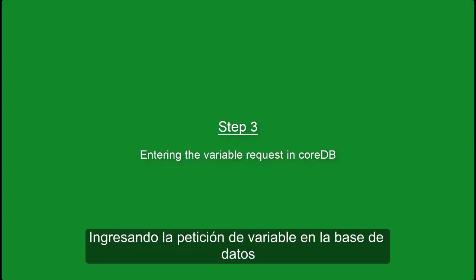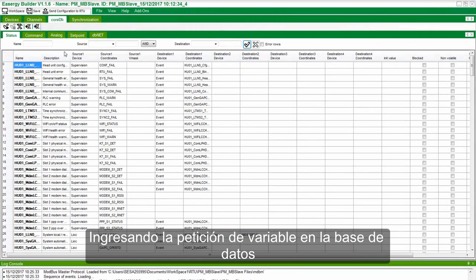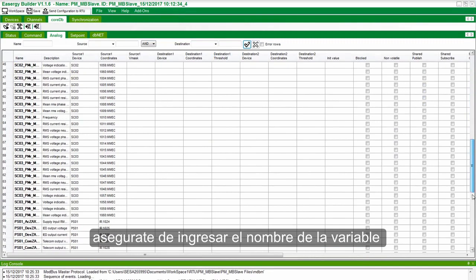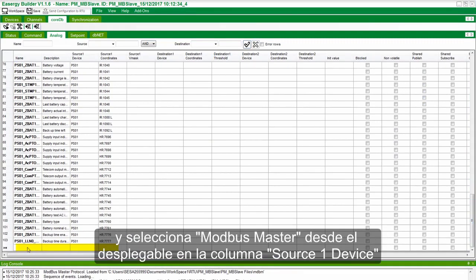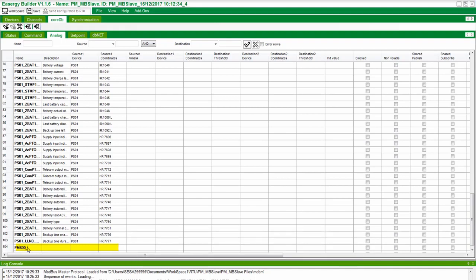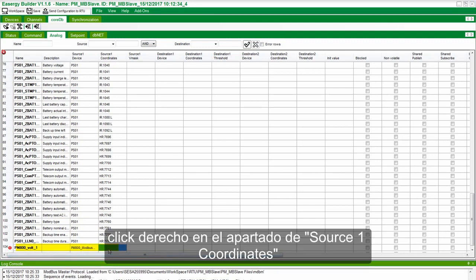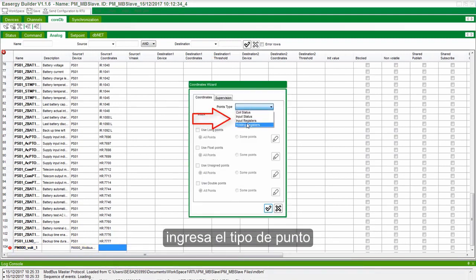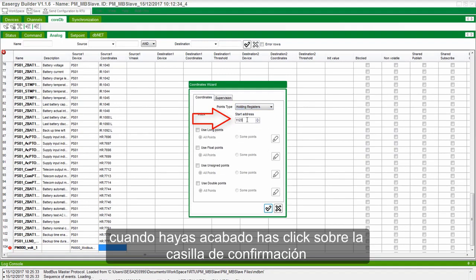Step 3: Entering the Variable Request in CoreDB. Click on the relevant CoreDB tab. Ensure to add the new variable name with the Source 1 device as the Modbus Master device from the drop-down. Right-click on the Source 1 coordinates and click Launch Point Wizard. Enter the point type and start address, then click on the checkbox when done.